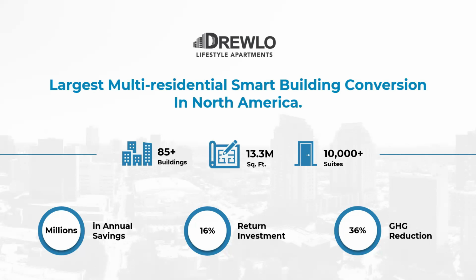But the reality we've seen from Drewlo, to get into some specific numbers: I said the traditional rule of thumb on boiler sizing in these types of MURB buildings was 25 to 30 BTUs a square foot, peak installed capacity. We're not really seeing operating values in these Drewlo buildings, of all ages, higher than 10 BTUs a square foot. So even when you build 50% redundancy on top of 10 BTUs a square foot, you're only at 15 BTUs a square foot, not 25 to 30, right? But the 25 to 30 was acceptable when we were just putting in simple, cheap boilers. But the delta in cost between a 15 BTU per square foot heat pump system versus a 25 to 30 is massive, right? Sure.